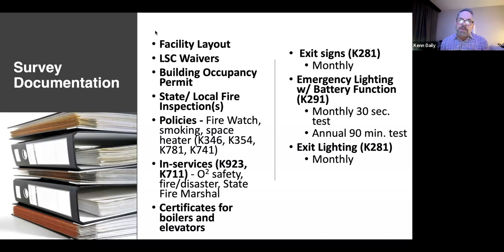And then in-services as well. K-tag 923 requires us to do an oxygen safety in-service, so that's oxygen handling, medical gas handling safety. You have your annual fire disaster preparation in-service. In some places, the fire marshal or local fire authority might come in and do an in-service as well. Again, you'd have all these agendas and sign-in sheets there, rather than trying to find them from your in-service coordinator when surveyors may ask about them. And then, like every state, boilers and elevators have certificates from the state agency. So again, you want to have a copy of those, making sure that those things are current in your building, that you're up to date.